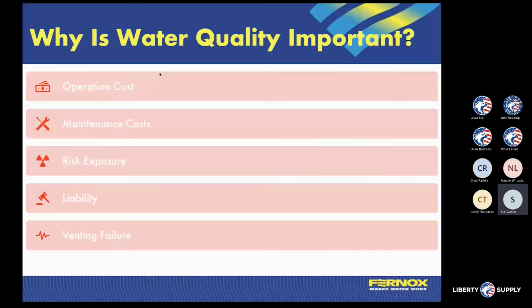When we talk about water quality, we talk about different aspects. One is operational costs, from the standpoint that if we have a system that is plugged up or sludged up or full of corrosion, the operation costs of that system, to put the energy from any type of heat exchanger you're utilizing into the physical fluid to create your energy transmission, are going to be higher, because you're going to have that system running for a longer duration to create that same operational efficiency. So it's going to have a better or worse operational cost.